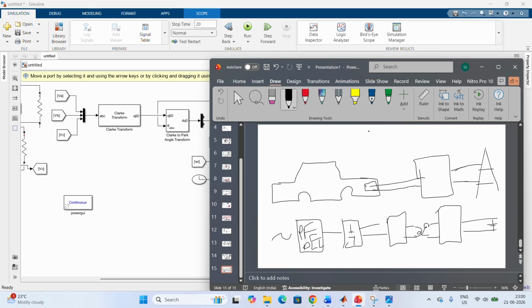Why there's a current controller is because, if you have a grid with a certain voltage, and you want to feed that grid, your voltage should be slightly higher. Only then can you start to feed energy into the grid. So basically, if you want to feed 3 kilowatts, you are always having a current controller. You will see that based on the grid impedance, or the impedance from the point of common coupling all the way to your socket.